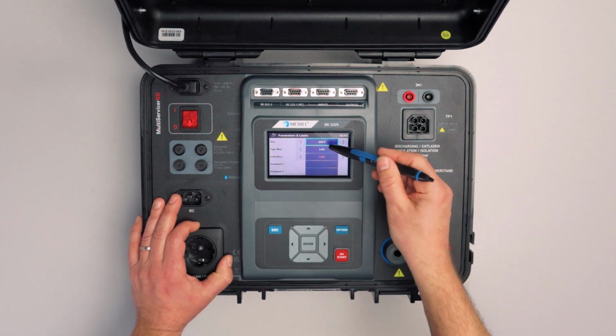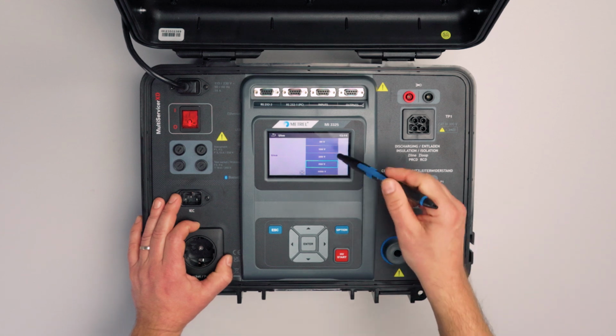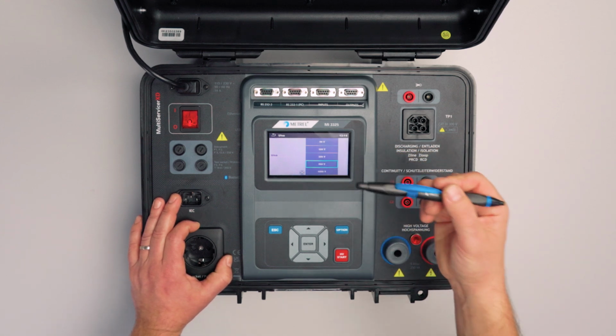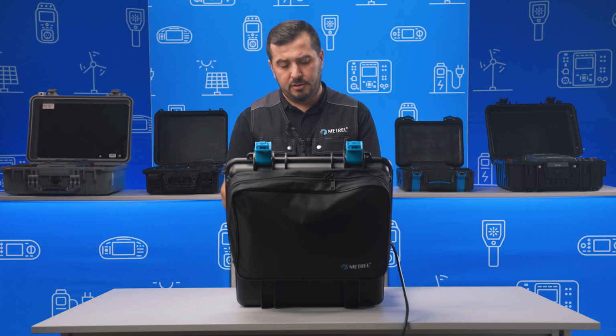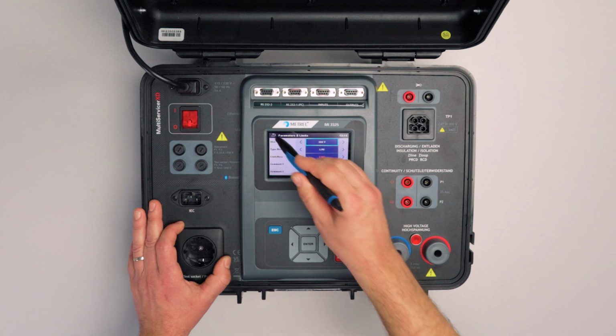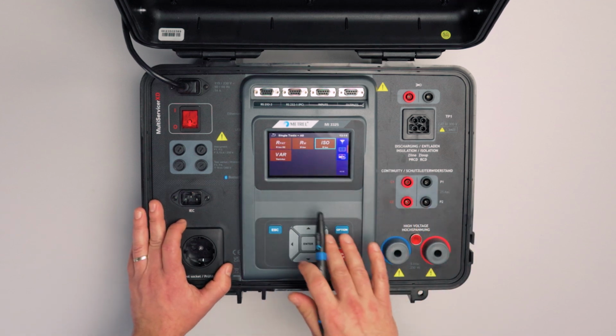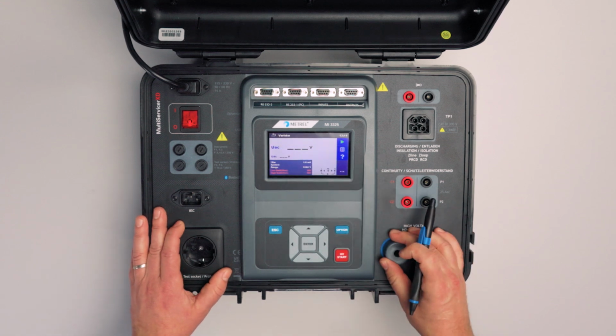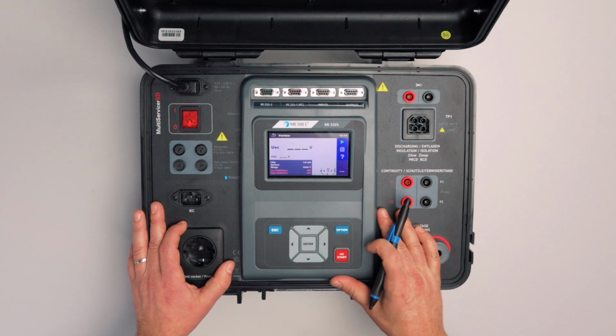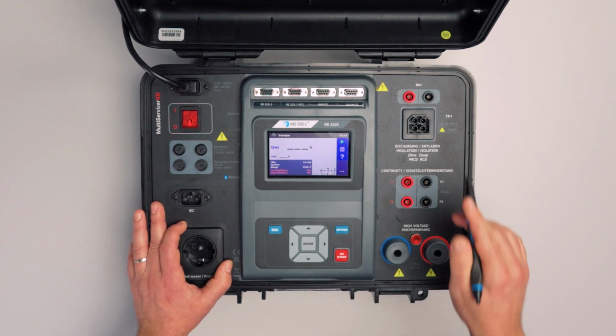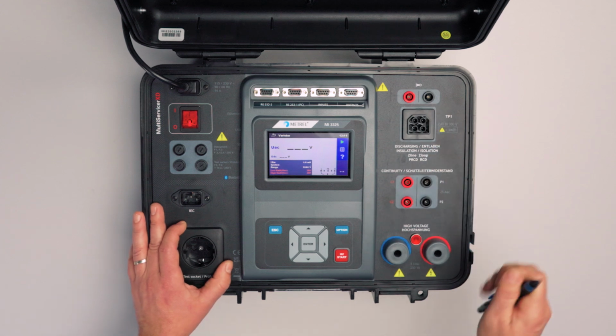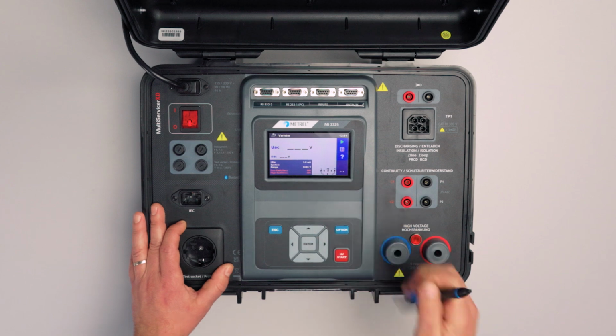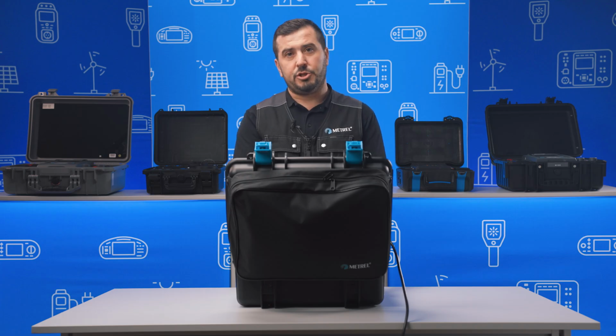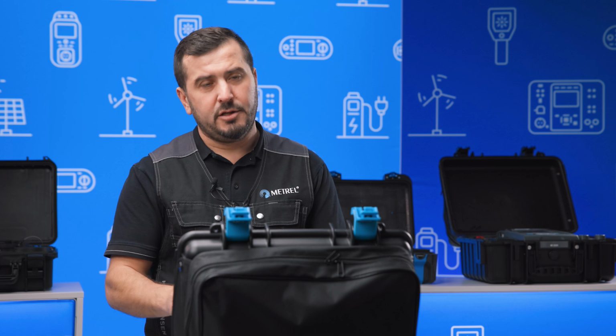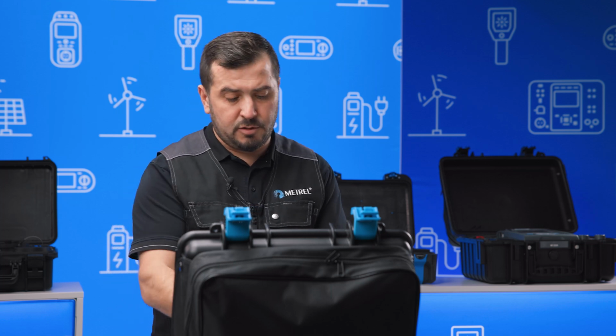Again, different parameters can be dedicated and also different test voltages can be used. We can choose between 50 volts, 100, 250, 500 and 1000 volts DC. The last option inside the RISO group is the varistor test. With this function, we have the option to also check the varistors. We have to use this universal testing port, and of course during the varistor test, the test voltage will be applied to the tested object by increasing the slope and checking if the varistor is okay or not.